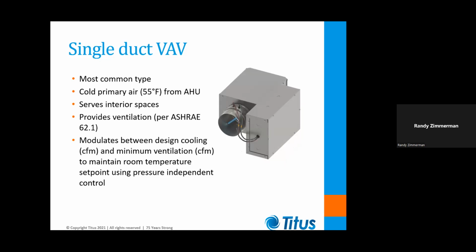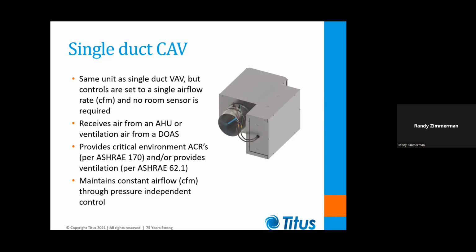We need to meet the ventilation requirements of ASHRAE standard 62.1 to make sure that we have adequate ventilation for our occupants. And the box is going to generally modulate between two preset flow rates. That would be our design cooling CFM and our minimum ventilation CFM. And then the damper is going to move in response to a wall-mounted room sensor to maintain room temperature while staying between those preset minimum and maximum flow rates.